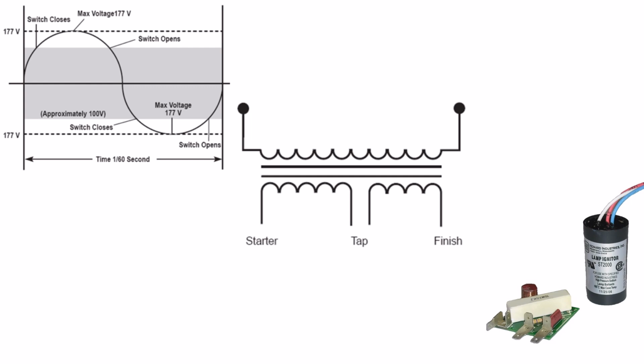If you're trying to fix or troubleshoot a high pressure sodium light, this is crucial to understand. If the lamp cycles on and off, it's not always the starter. If you've mixed incompatible ballast, starters or lamps, you'll get weird symptoms. If the lamp isn't starting, check that the starter is matched to the fixture and the capacitor is good. And remember, even though the starter looks like a small part, it's handling thousands of volts. So be careful. Always disconnect power before inspecting or replacing components.